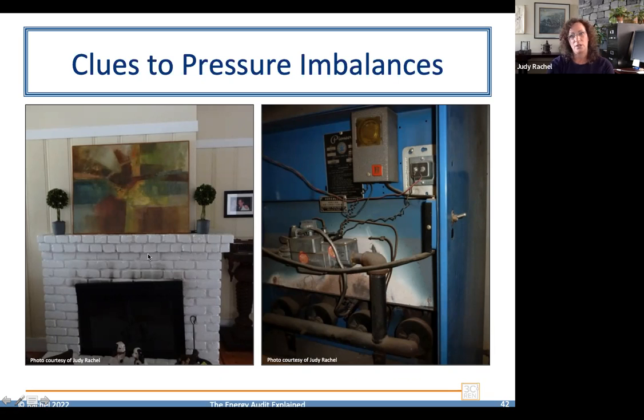So then I can start asking other questions. Do you notice when the smoke comes out? Do you happen to be using your furnace at the same time that you're using the fireplace? Do you use the fireplace and not open any of the windows in your home? So there's a back and forth between what the homeowners might know is going on in their homes without actually knowing the why, and you knowing what clues are telling you about, say, the pressures in the house, and trying to suss out what's going on and how you can fix these things. And then this was a flame rollout from a furnace. And once again, the only reason that's going to happen is if there's a pressure imbalance in the area of the furnace itself.